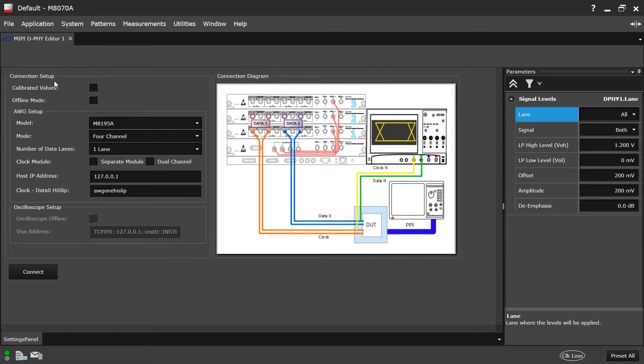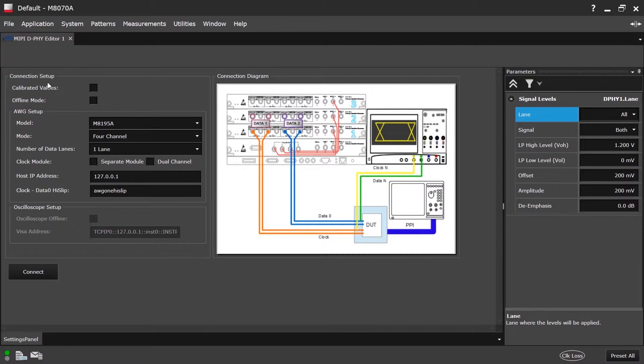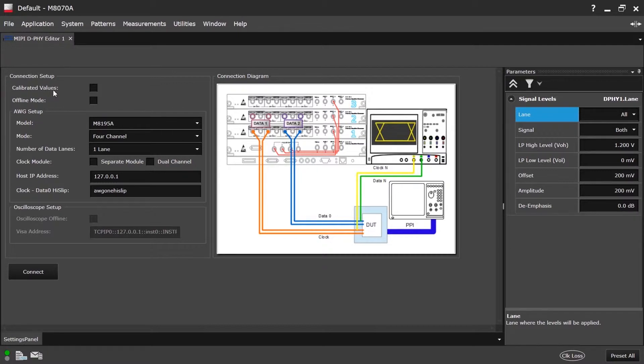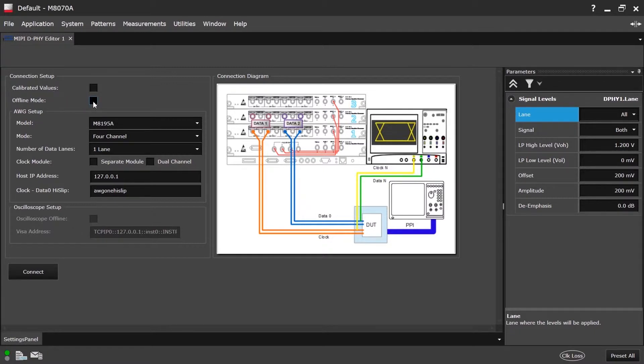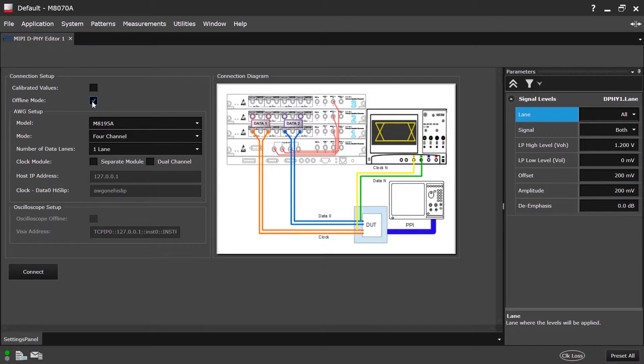Let's look into the details about the Connection Setup panel. I will go through them step by step. First, we can see the Calibrated Values option. This option is to run the D-PHY Editor with calibrated values which are obtained by running the calibrated procedures. These are a part of the D-PHY CTS plugin. This will be covered in a different video. Next checkmark is the Offline Mode, which is used when we want to run D-PHY Editor without connecting to real instruments.